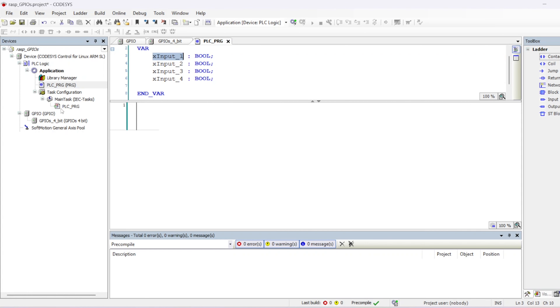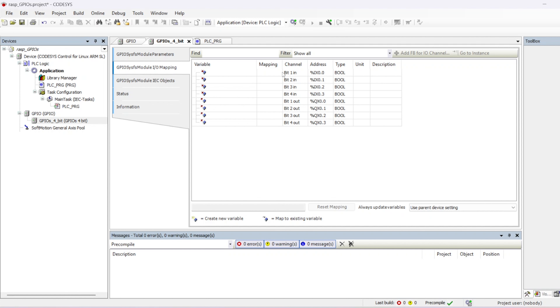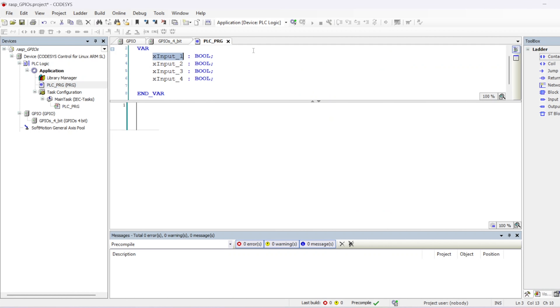How do we use the GPIOs in our code? Go to the GPIO module's IO Mapping — each channel represents one GPIO and has one address. Inputs start with '%IX' and outputs start with '%QX'. Using these addresses, I can capture the status of each GPIO and use that in my code. I'll map each channel address to one of the four variables I declared.